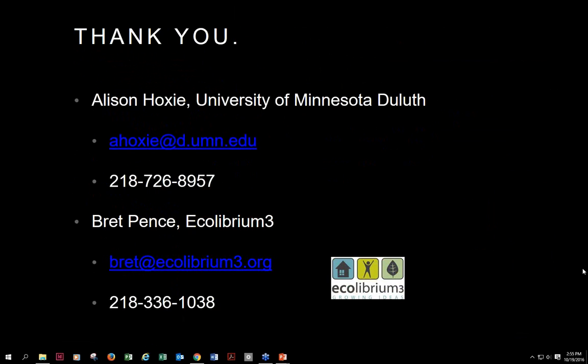That was one consideration for us. In talking to SunVerge and other technical assistants, they all agreed that installing it inside was better for this climate. The mechanical room it's in is a little warm because there's other mechanical equipment in there. In the wintertime, it's regularly 75 degrees, where the rest of the building might be heated to 65. So it's something we'll keep an eye on, but when looking at where to put it, that was a point of concern we worked through early with SunVerge and our technical advisors.